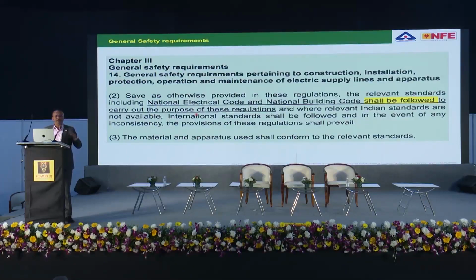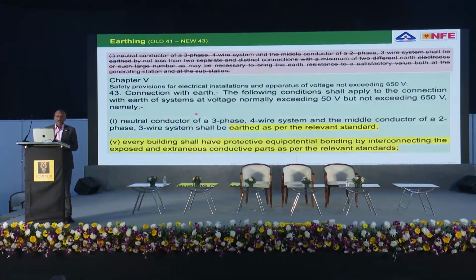I will just take you to a few of the code of practices, a few of the regulations. I don't want to explain all the regulations. It takes a lot of time. One of the regulations which is very favorite to me is about earthing, for example, which is a very confusing subject all over India. So now the regulation says every building shall have protective equipotential bonding by interconnecting exposed and extraneous conductive parts as per the relevant standard.